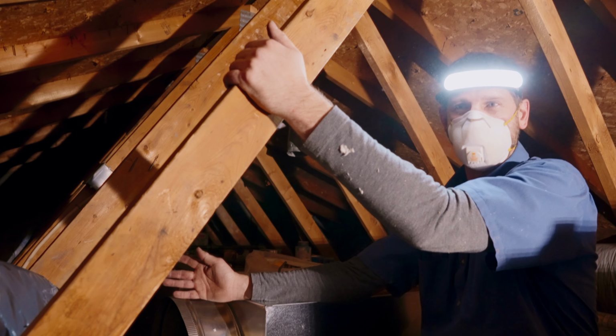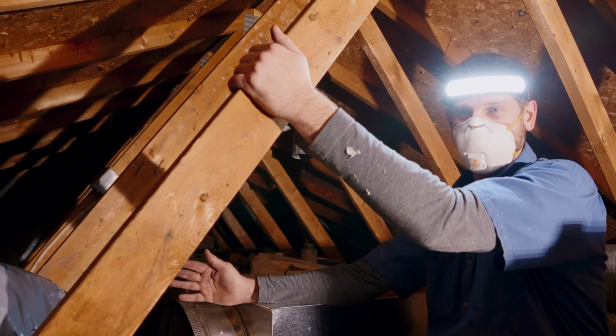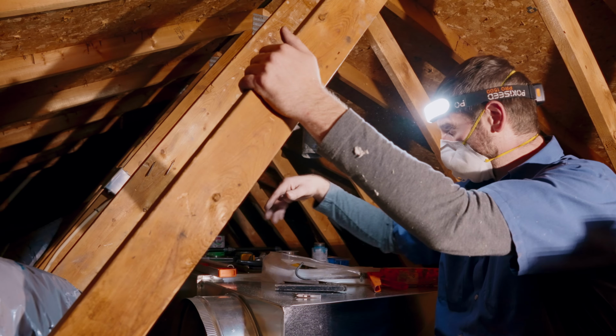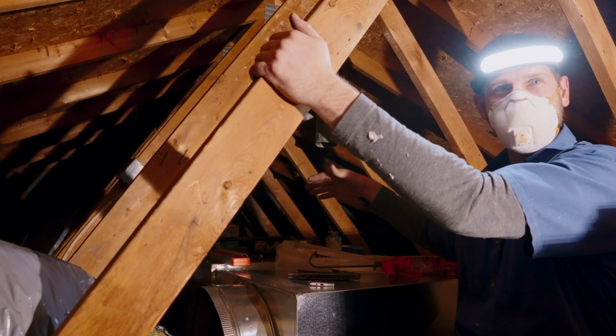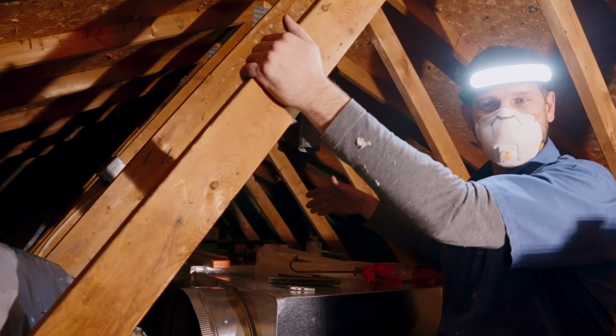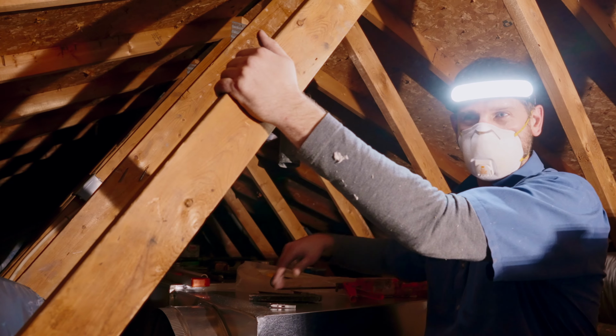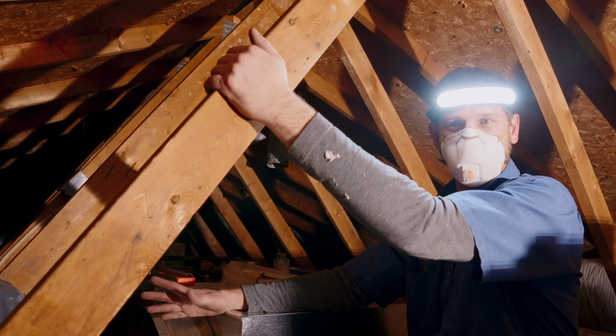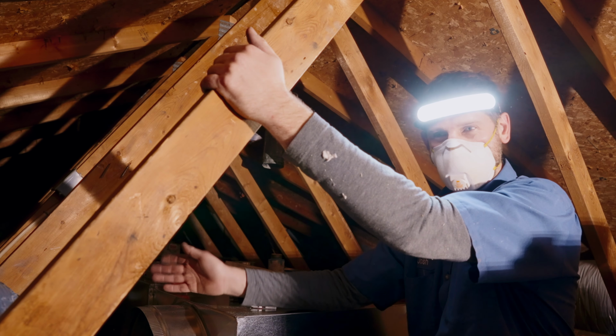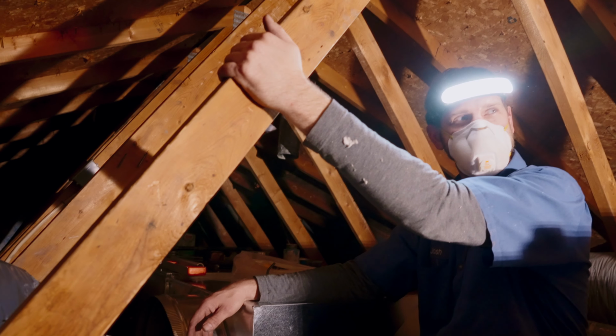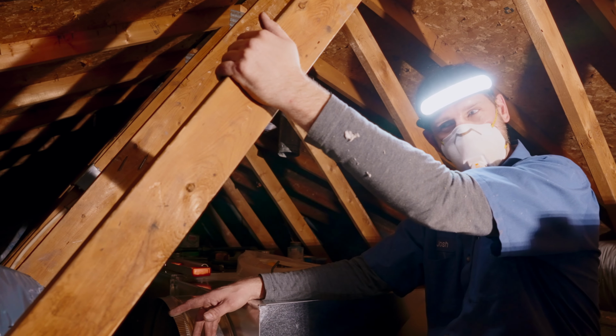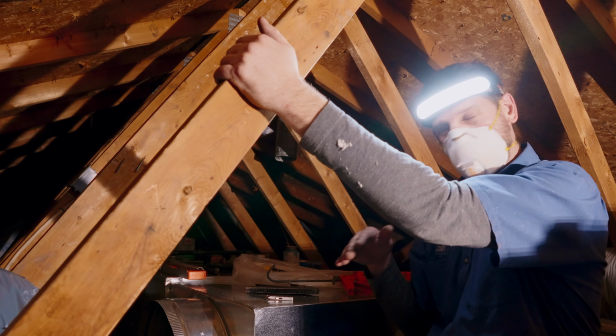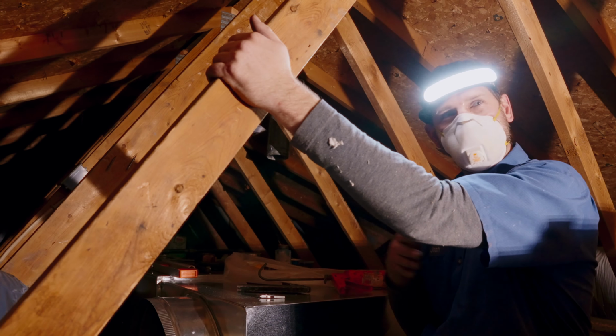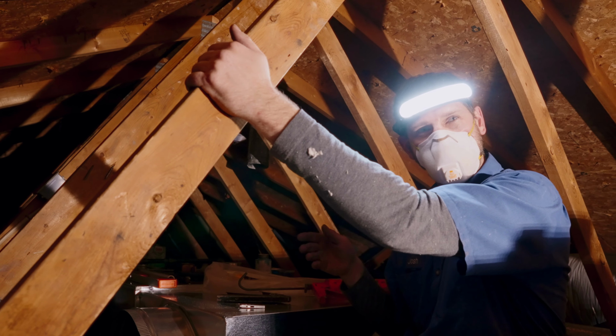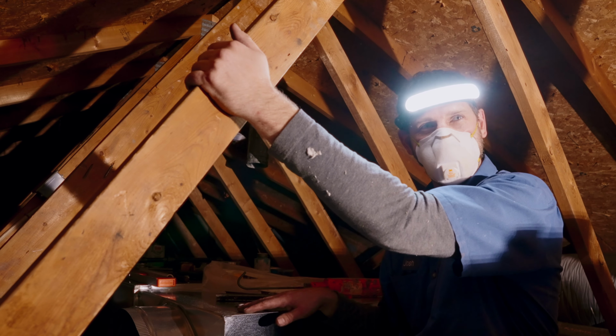So if that return is clogged, like a clogged filter, you're heating this up, there's nowhere for that heat to go. Your furnace is just gonna get hotter and hotter. And years of doing that, it's getting really hot and cooling off. It'll definitely crack your heat exchanger. In the summertime when you're running your cooling, if you get a clogged filter, your coil can't breathe, no airflow over it. It's just going to get colder and colder and freeze up, turn into a big block of ice.